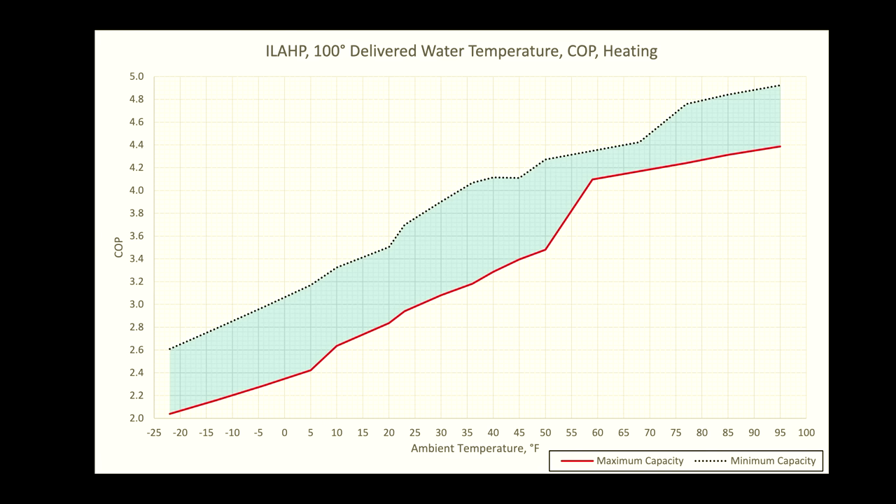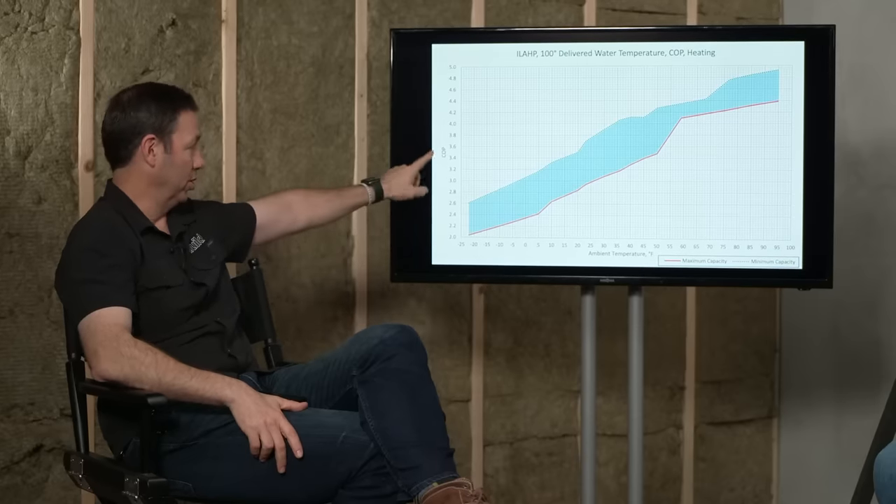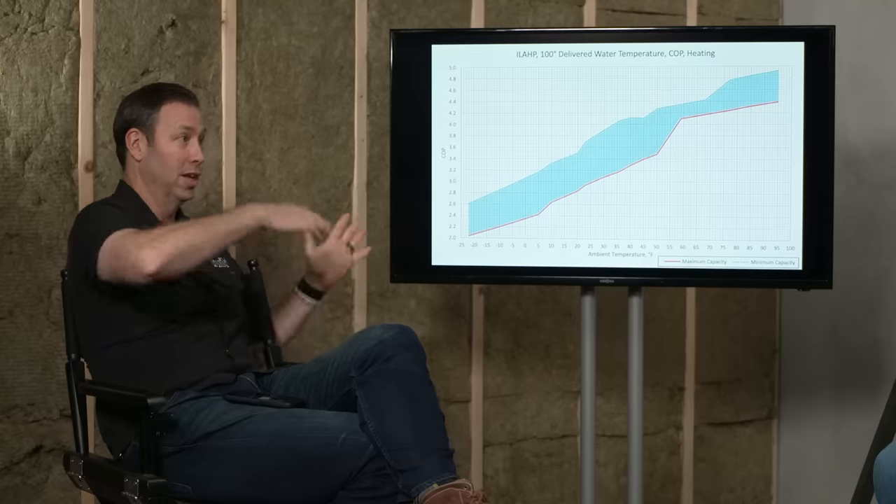Let me show a chart for the ILAHP — this is the current unit I have sitting next to me. The verbal version: at 100-degree water output, the warmer the ambient temperature outside, the more capacity this system can potentially make. The bottom scale is ambient temperature in degrees Fahrenheit — down to minus 22 on the far left, up to 100 degrees on the far right. As you angle upwards, the scale on the left is the coefficient of performance — in other words, when I put one kilowatt in, how much heat am I going to get?